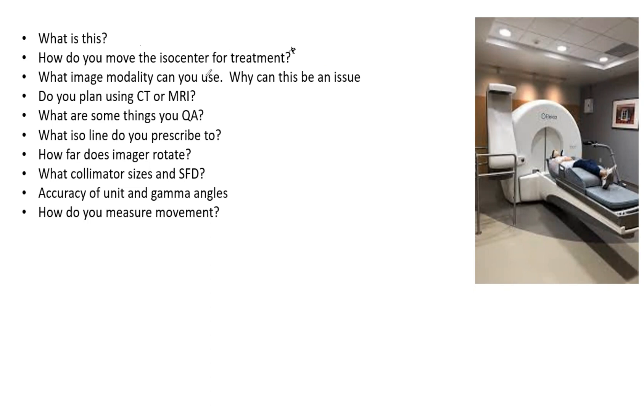What image modality can you use? You can plan on and use MRIs, but watch for geometric distortion, especially at the periphery. The Icon has a cone beam CT attached to it on this little arm right here. Do you plan using CT or MRI? MRI gives no heterogeneity correction, but since the brain is so close to water, that is okay, and there's only about six millimeters of skull. You can use MRI, you can use CT, or a combination of both. Know not just that you can use MRI, but why — because there's not much heterogeneity in the brain and the skull is so thin.